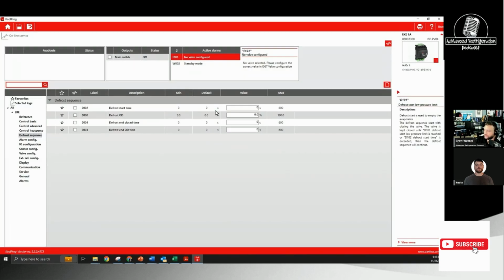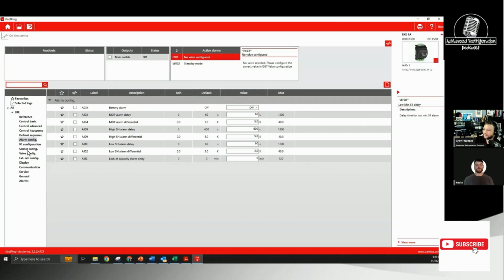Defrost sequence - we can actually do a defrost on here because you have an additional digital input for that. Defrost end time. You could probably also use it for valve recalibration, so how every so often a lot of the drivers close - once a day or once a week - just to make sure they go back home so they don't come out of calibration. Let's see, MOP delay, battery alarm, superheat high differential, superheat low differential.